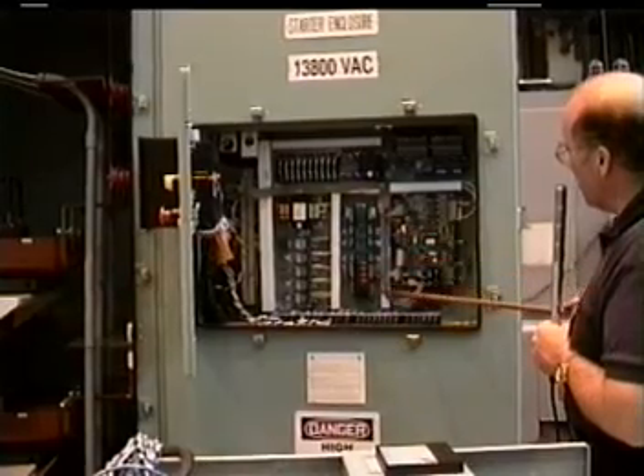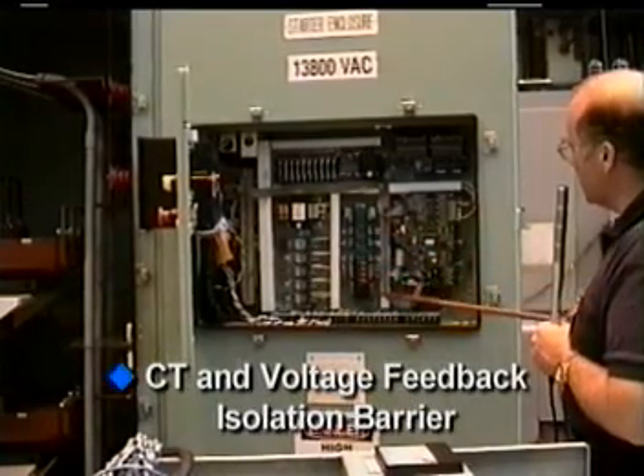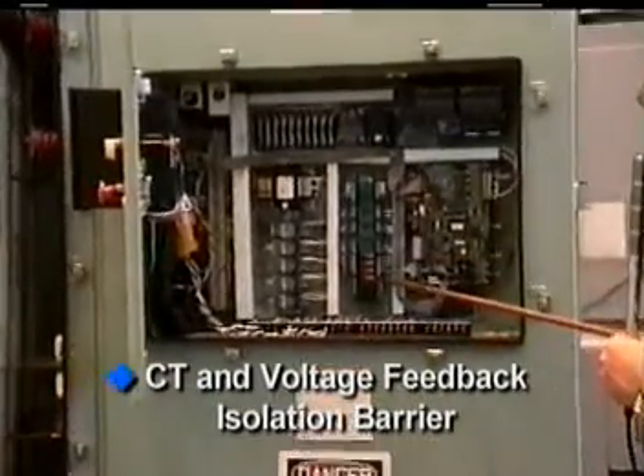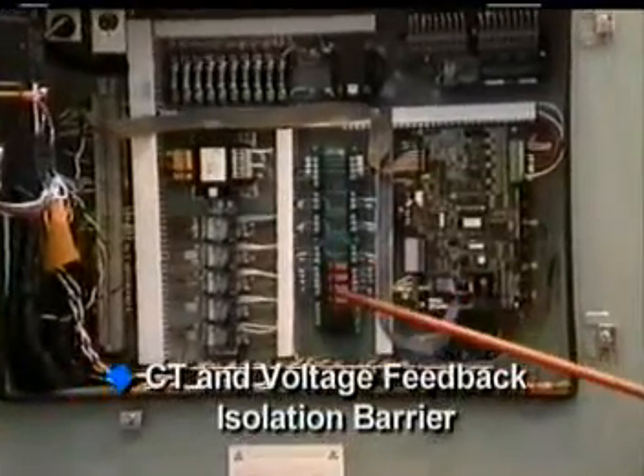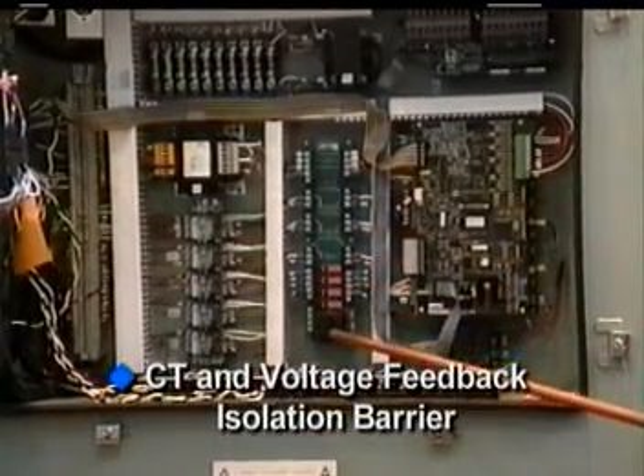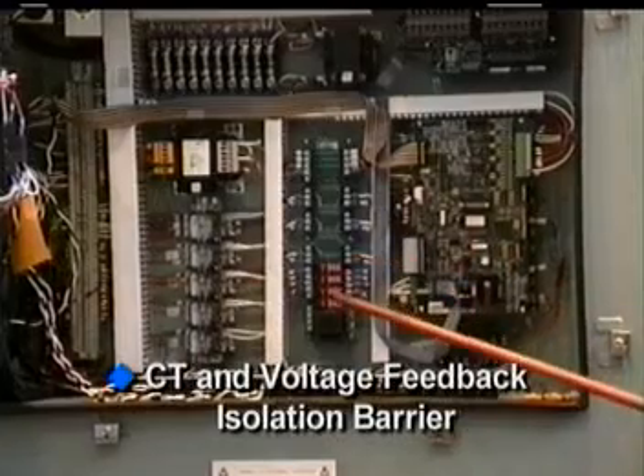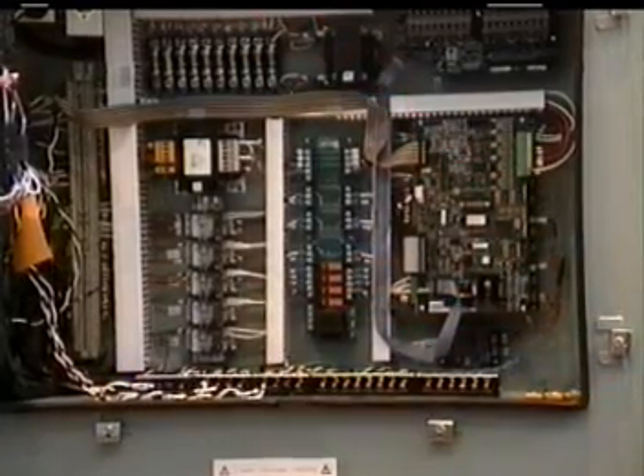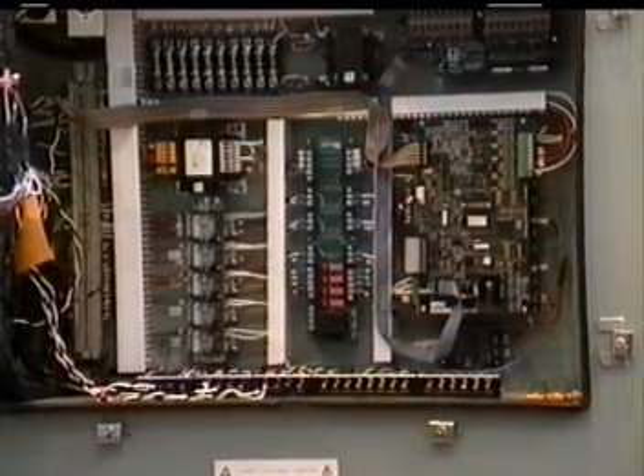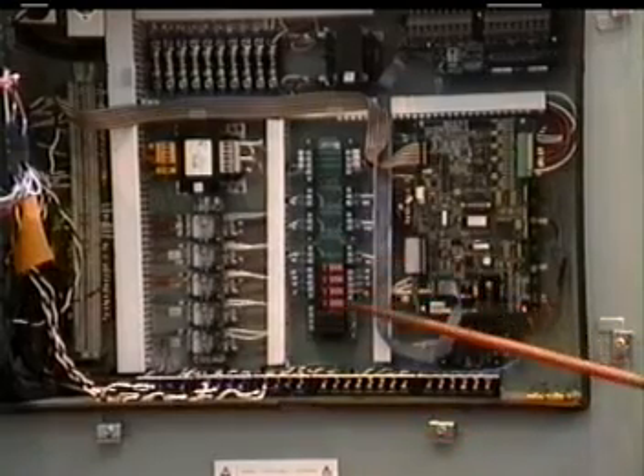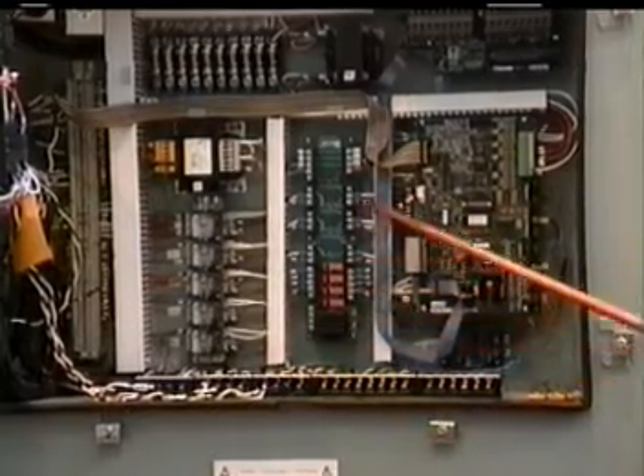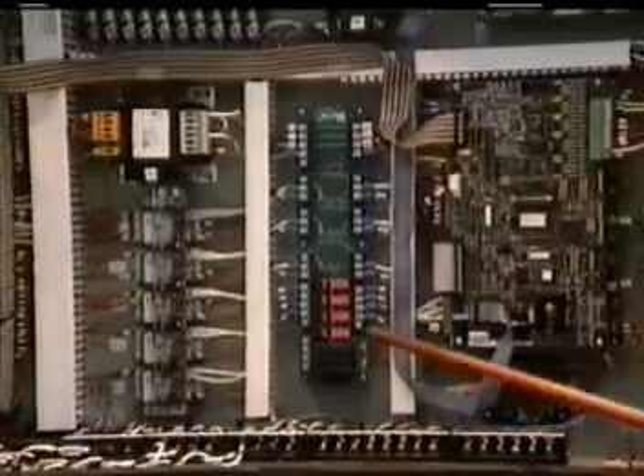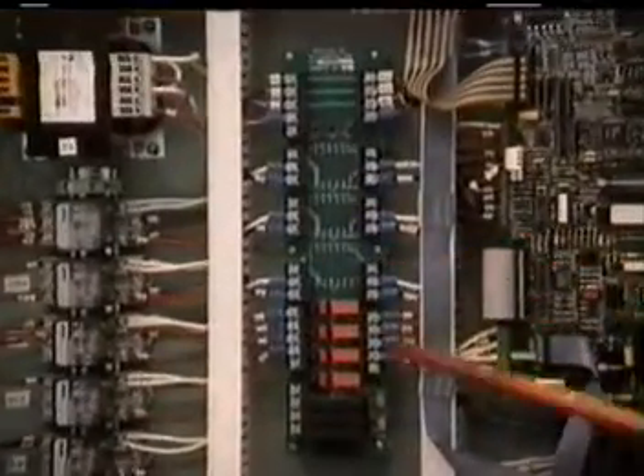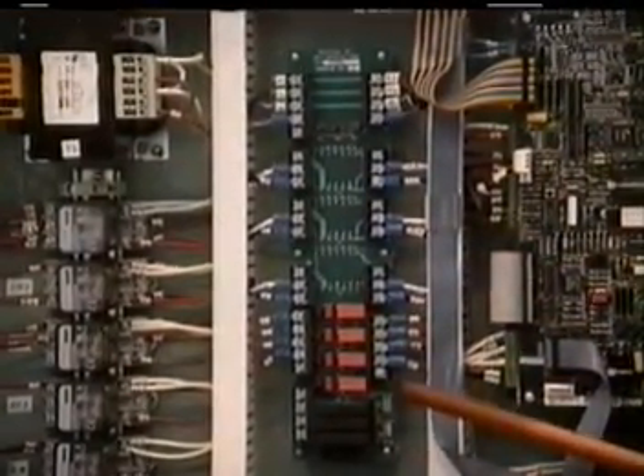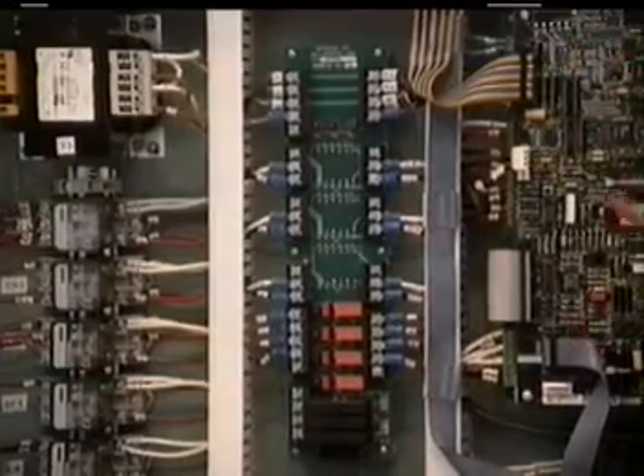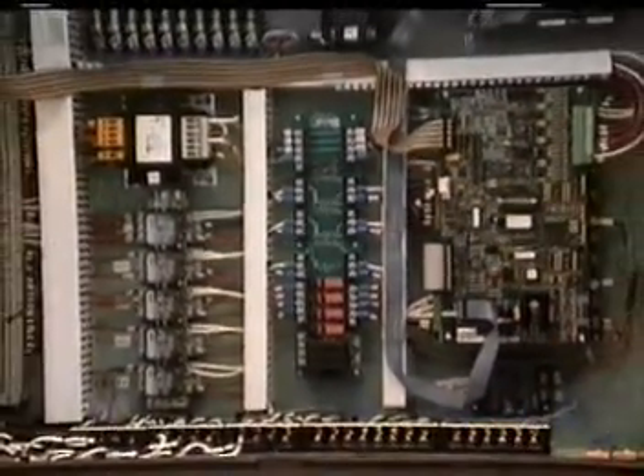This board over here provides the barrier between the high voltage and the low voltage from the resistor divider card, as well as from the CTs within the input section to the assembly. The purpose of this board is to provide a barrier so that we can clamp any transient voltages to a lower magnitude before they enter into the microprocessor section here.